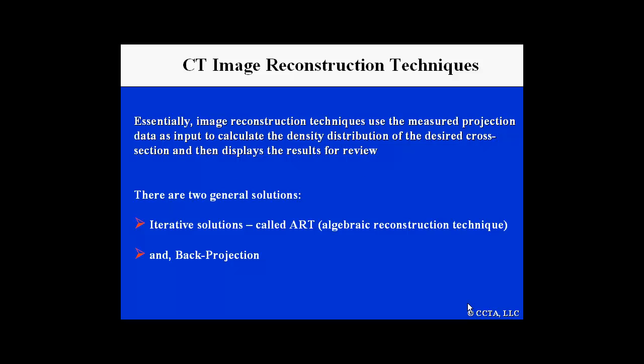Image reconstruction by CT uses the measured projection data as input to calculate the density distribution of the desired cross-section and then displays the results for review. There are two general solutions for reconstruction algorithms: an iterative solution developed many years ago, originally called the ART algorithm or algebraic reconstruction technique, and the one that is more commonly used today, which is called back projection.